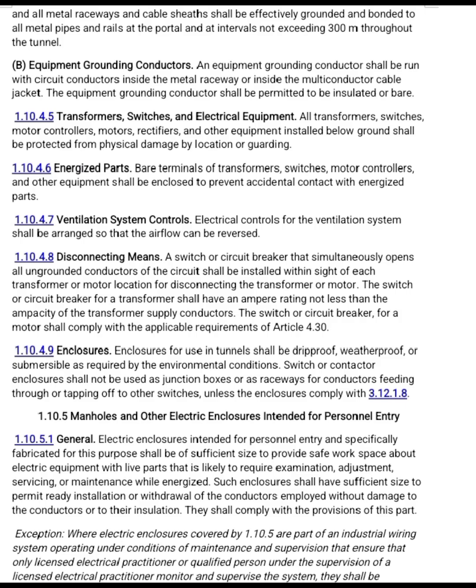1.10.4.6 Energized parts. Bare terminals of transformers, switches, motor controllers, and other equipment shall be enclosed to prevent accidental contact with energized parts. 1.10.4.7 Ventilation system controls. Electrical controls for the ventilation system shall be arranged so that the airflow can be reversed. 1.10.4.8 Disconnecting means. A switch or circuit breaker that simultaneously opens all ungrounded conductors of the circuit shall be installed within sight of each transformer or motor location for disconnecting the transformer or motor.